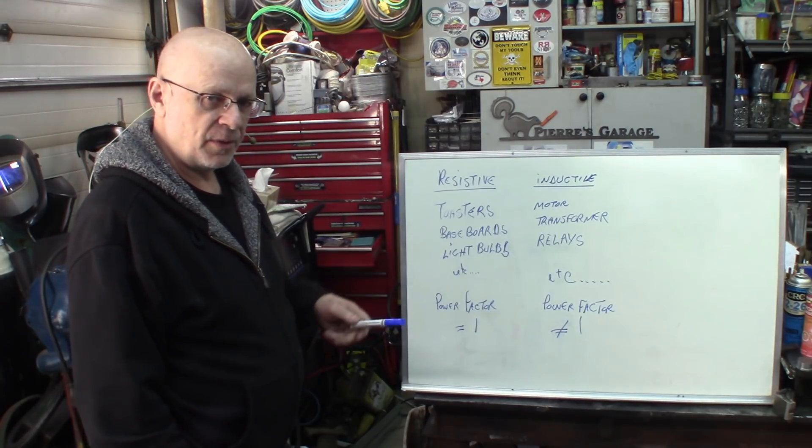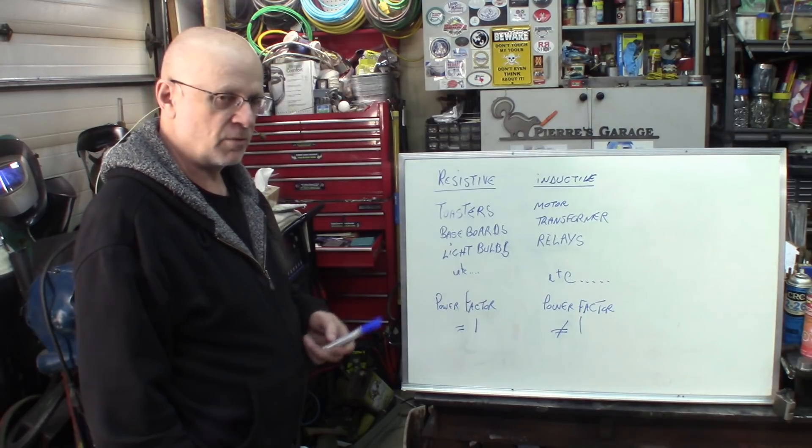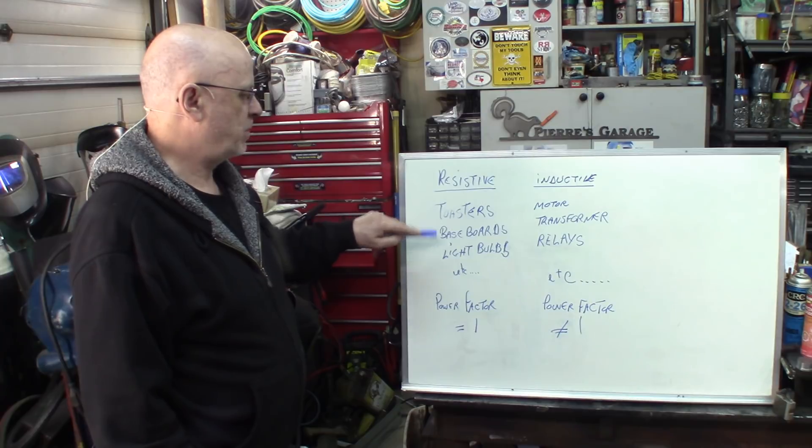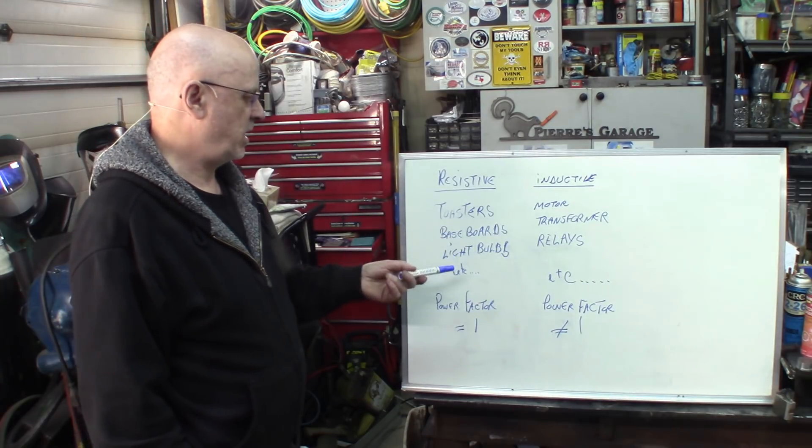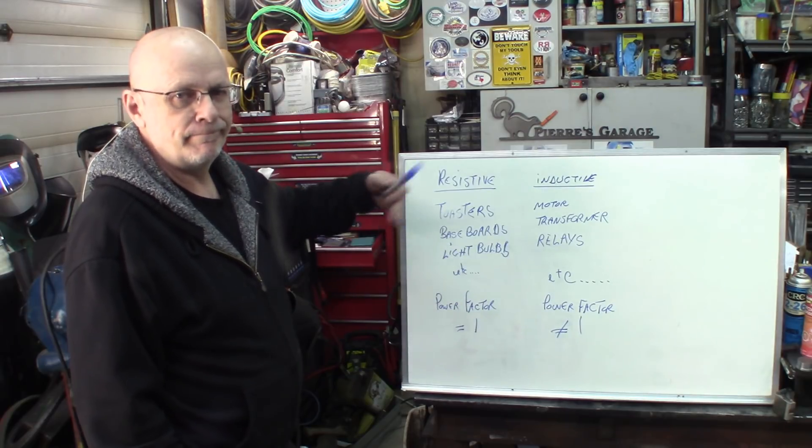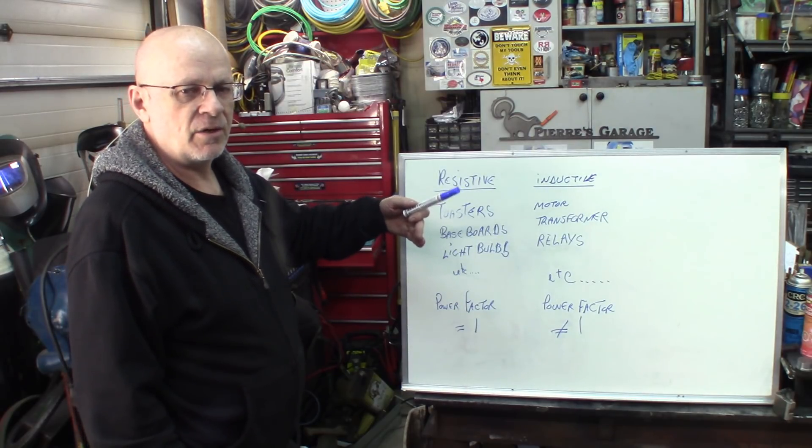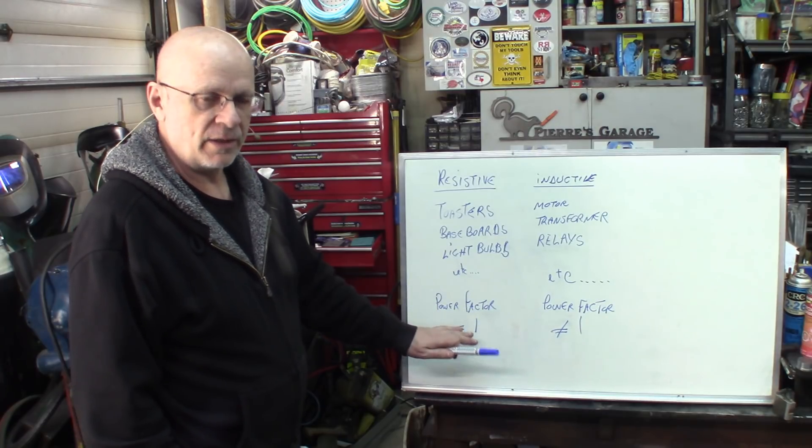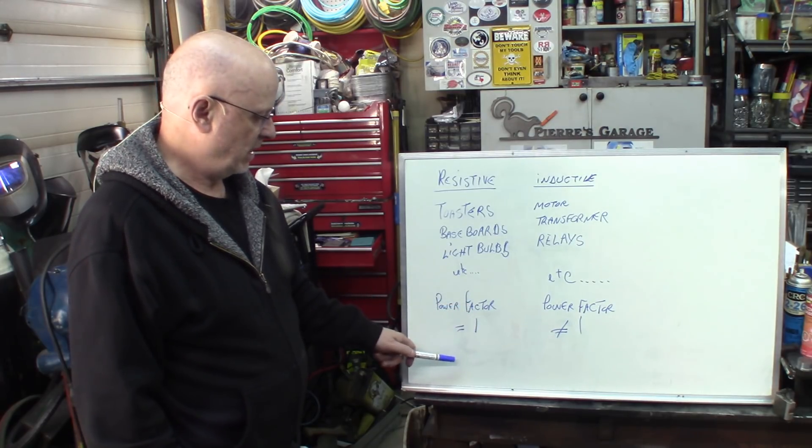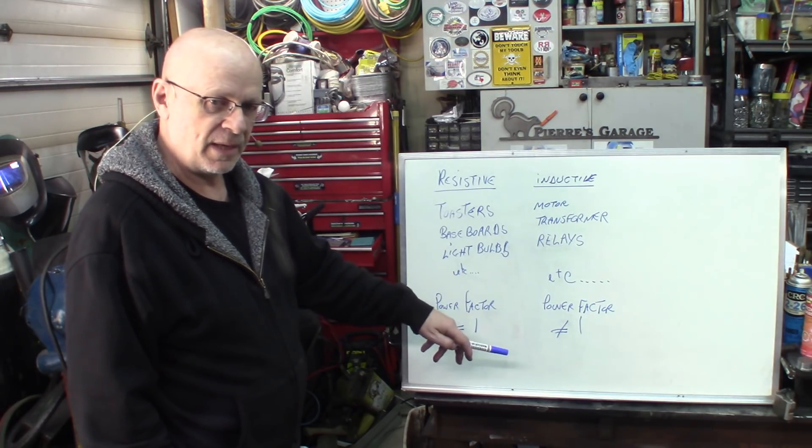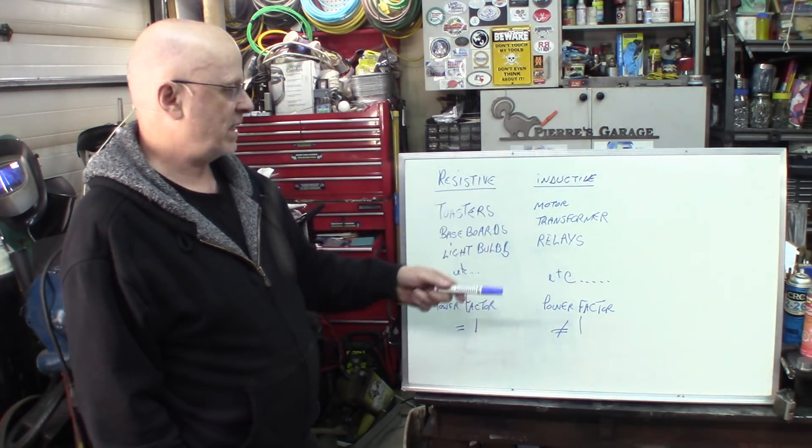To help you make the difference between what's inductive and what's resistive, there are just a few examples. Resistive loads: toasters, baseboards, incandescent light bulbs. They're very near to 100% resistive loads. So the power factor will be considered to be around one or very close to one. So the calculations for power formula with voltage multiplied by amps will be exact in this case.